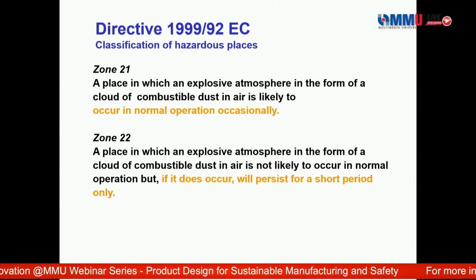The same classification applies to dust, but the zone designation has the letter 2 in front, followed by a number showing how severe the environment is. Zone 2-1 is where dust is present occasionally during normal operation. Zone 2-2 is where it only exists for a very short period of time.